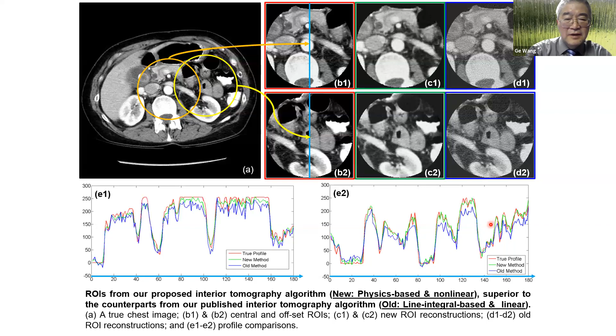If you just assume a linear integral, there will be some problem, because real data is not monochromatic. Really, you use a polychromatic X-ray beam. So we can use a nonlinear model to perform interior tomography. Comparing the old and the new method, the new one shows significant improvement. In the old method you assume a line integral. The new method assumes a nonlinear model taking the polychromatic X-ray spectrum into account.